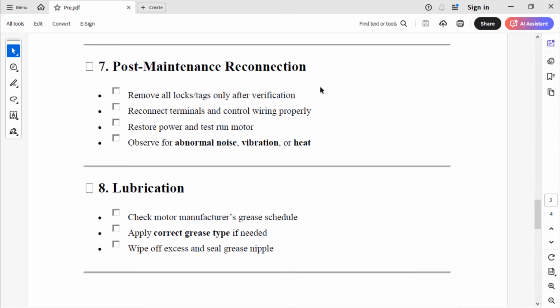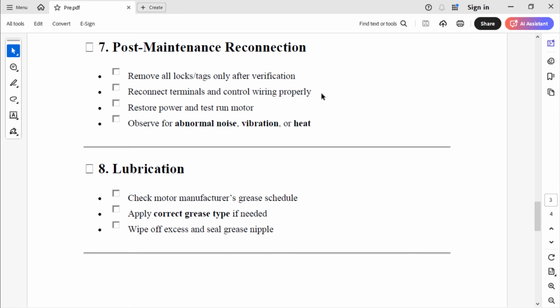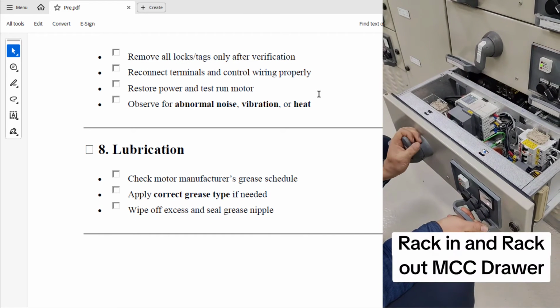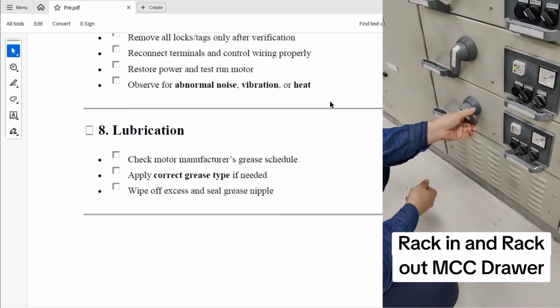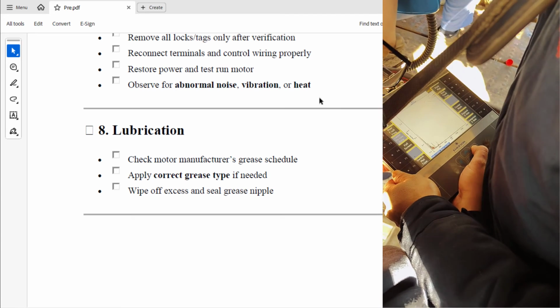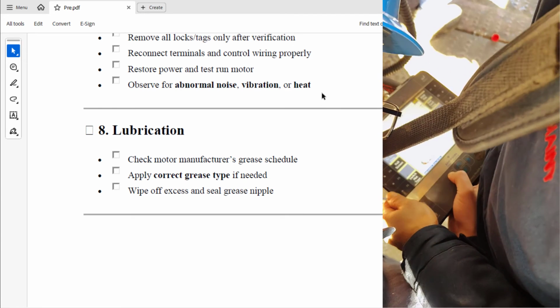Post-maintenance reconnection: we remove all locks and tags only after verification, reconnect terminals and control wiring properly, restore power and test run the motor. Observe for abnormal noise, vibration or heat.